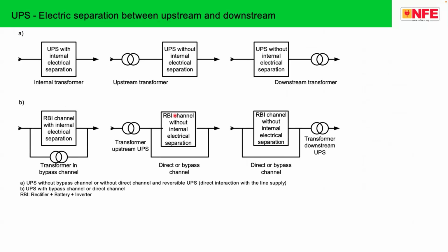Use of UPS. Most often, we have the habit of using UPS without an isolation transformer. The technical word is electrical separation. We have a three-phase UPS, there is no separation, there is no isolation transformer, and the loads are single phase, which need a neutral. Now the neutral from the main supply is sometimes used, which creates confusion and creates circulating current in the entire system. The ideal situation for a hospital is to have a UPS with an isolation transformer.